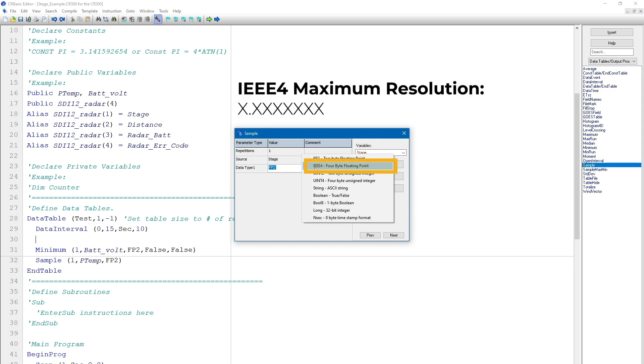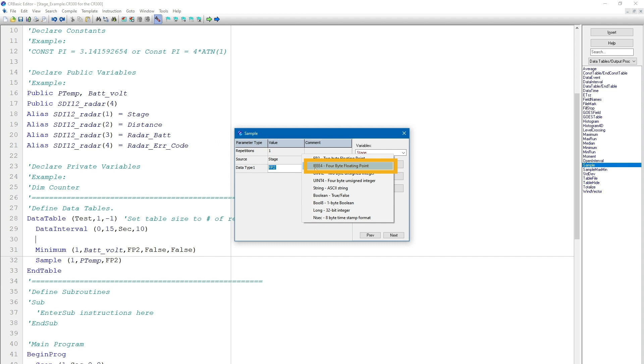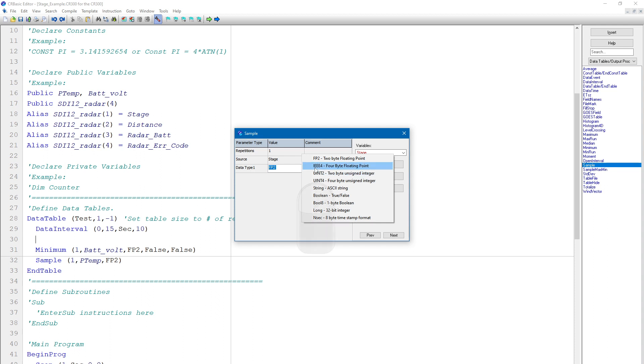But if I use the IEEE4 data type, I can report stage values with up to 7 digits of resolution. The trade-off for using IEEE4 is that this format uses twice as much storage memory as FP2. So don't use high-resolution data points when they're not necessary. In this case, because my stage value could exceed 79 feet and I need 1 100th resolution, I will choose the IEEE4 data type.